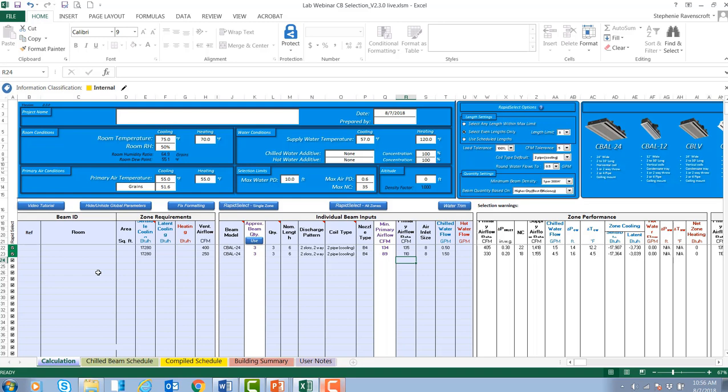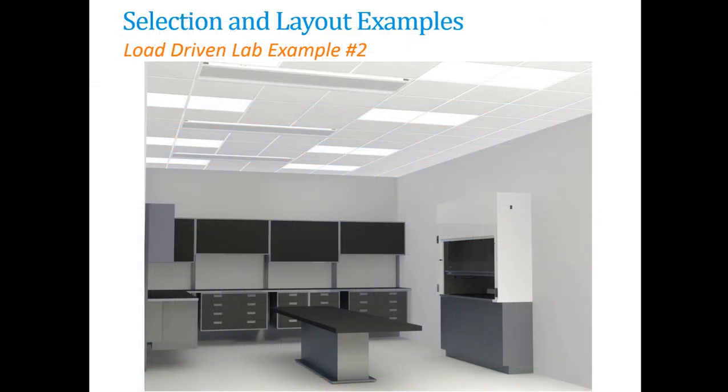By increasing the total supply airflow rate to the space by only 80 CFM over the 250 CFM minimum, we were able to achieve an additional 10 percent reduction in outdoor air from the constant volume approach. This is a great example of why using active chilled beams in load-driven labs is especially popular due to the vast energy savings that can be achieved.